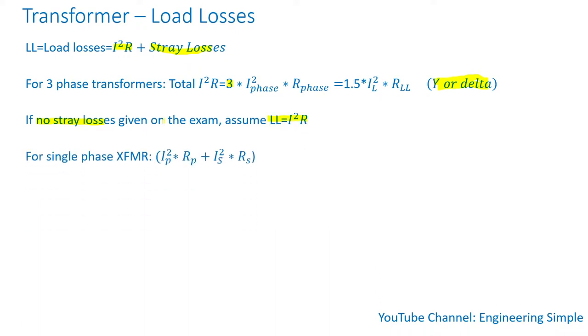For single-phase transformers, the total I squared R is just the primary current squared times the primary resistance, plus the secondary current squared times the secondary resistance.